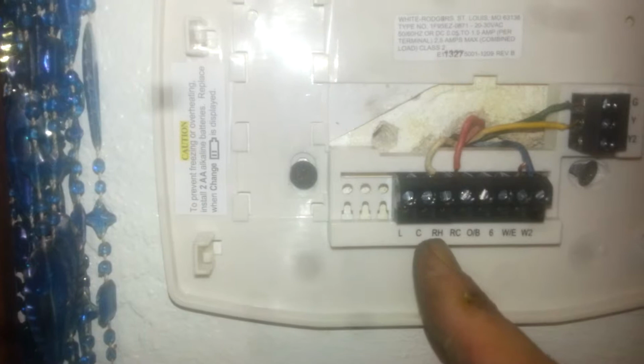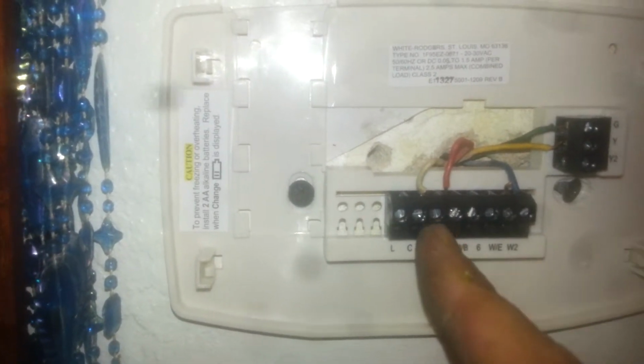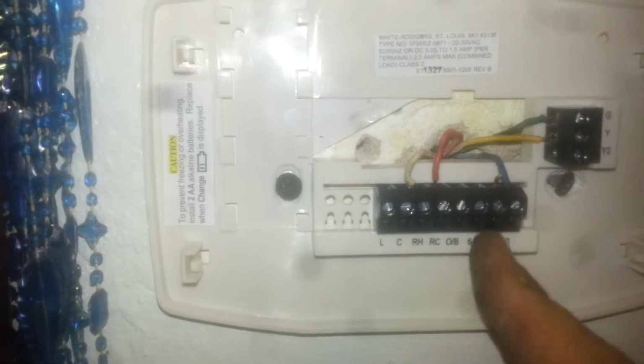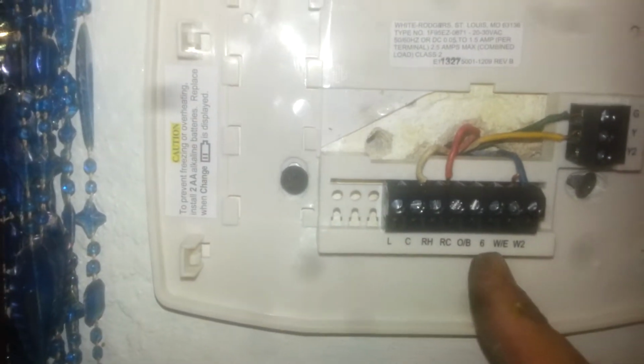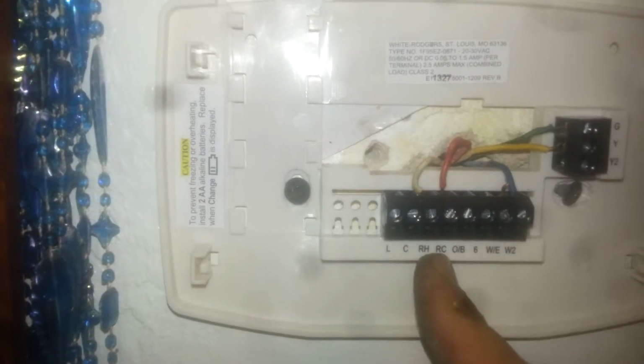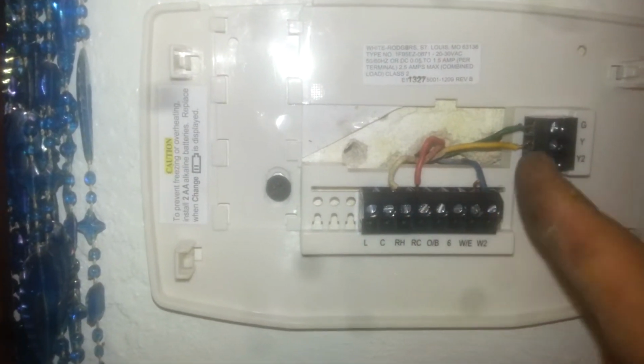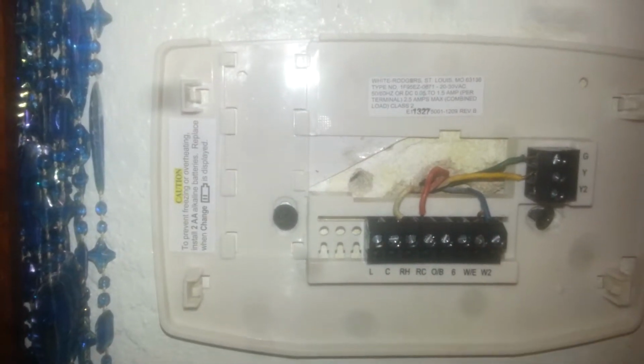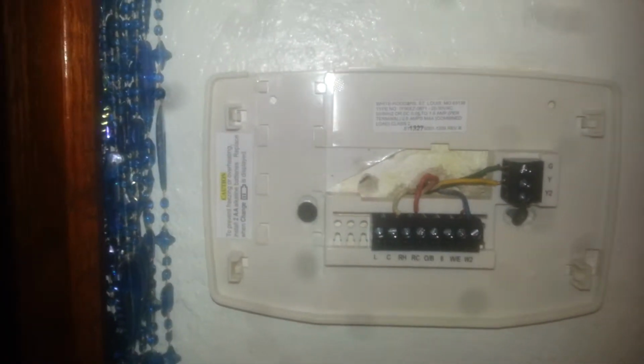That jumper I took out, and the reason you take this jumper out is because it's used when you're using two transformers. RH is obviously for red heat, and this is what turns on the heat mode from the thermostat. So I got that connected to RH to W, and then the red, which was coming outside from the transformer, going in for the yellow, to make this a complete circuit for the thermostat calling to the condenser for cool and to the furnace for heat. So that's how I hooked that up.